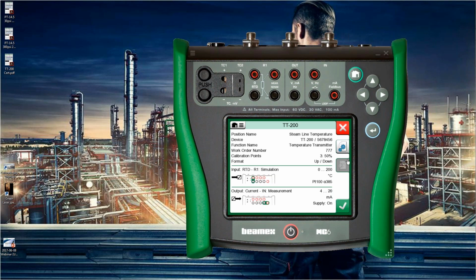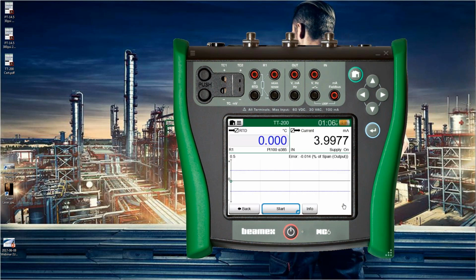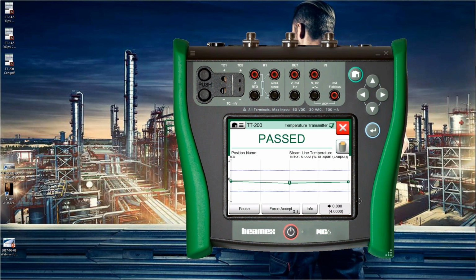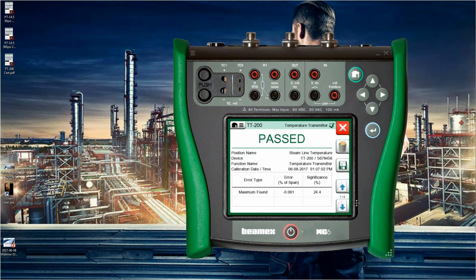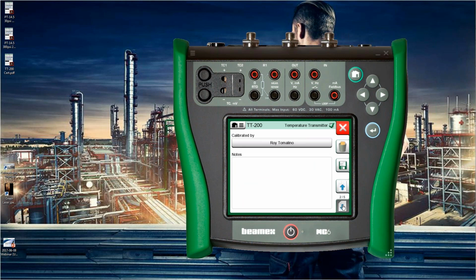and what's my tolerance? 0.25% of span, that's what it is. So there's no zeroing here because it's all electronic. So let me just hit start. I'm doing a 3-up-down test, I believe. I just had a 2-second delay in between each test point. So now we're doing the span. 100 degrees is our midpoint, so we're coming back down again. So this is a pretty quick 3-up-down. I just wanted to jam through this.